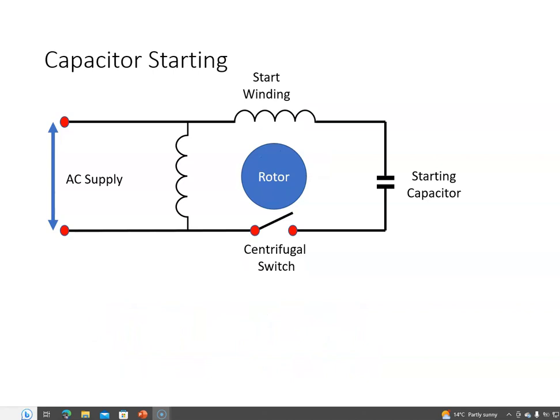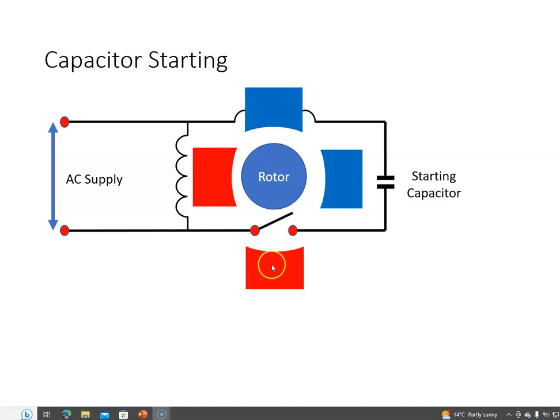When we add the start winding and the capacitor, the values are chosen so that current flowing in this branch of the motor is 90 degrees out from the current in this branch, and the effect of that is that it gives me a second electromagnet 90 degrees removed.